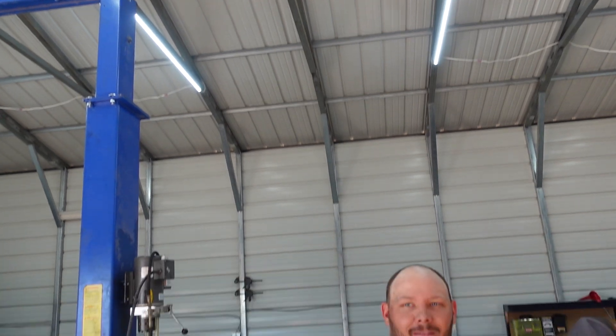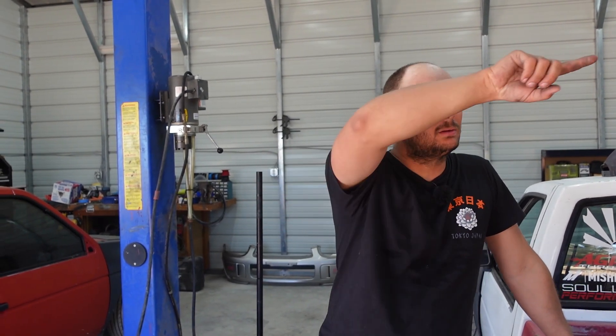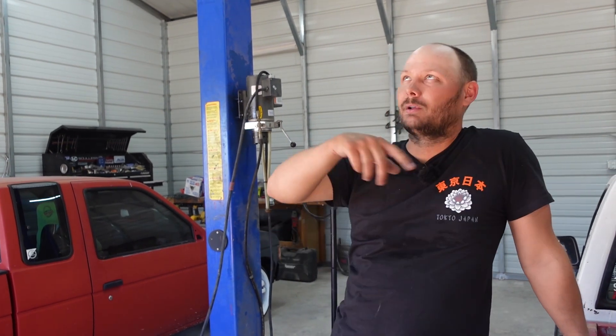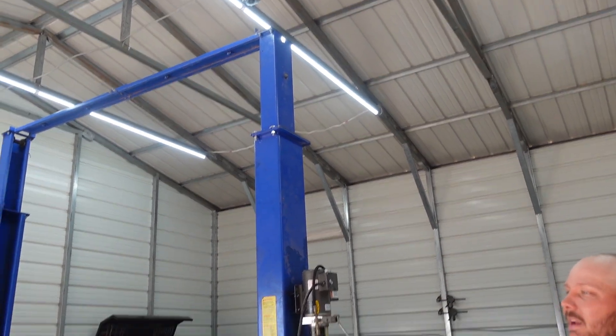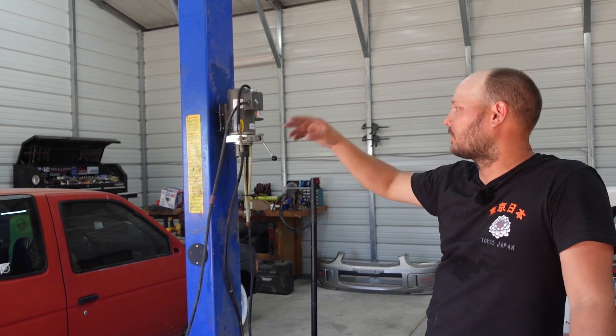Look at me for half a second. You're going to get a double breaker — a two-pole. You're going to put a black wire in one side and a white wire on the other side, and then the ground to ground. If you were doing a single pole circuit, it would be black wire to the breaker and then white wire to the common rail inside there. So you go to the common and then the ground to the ground. But because it's 220, you need both to have 110 on each side, so you run both of them in there and the ground just is the ground. So anyways, 10-2 armored goes up, goes over, goes over, goes down. And we have a box over there where it's just dead-ended, so that when we get our new compressor, we already have power there and we can run it straight out — the lift and the compressor will be on the same circuit.